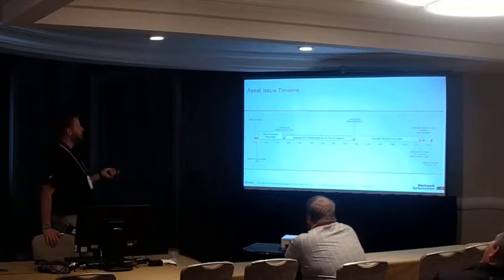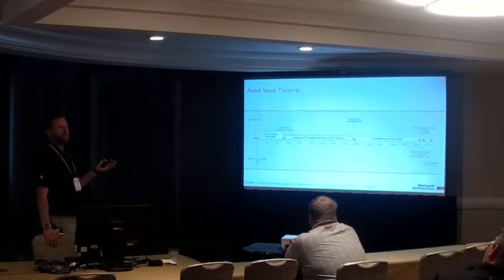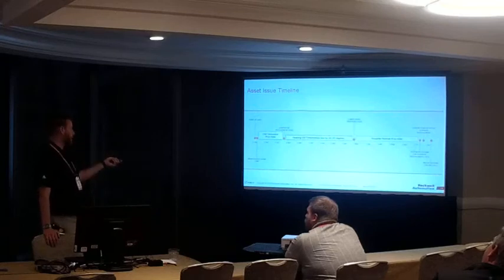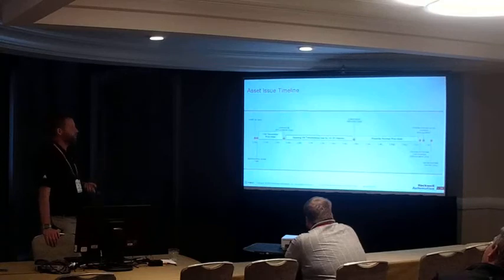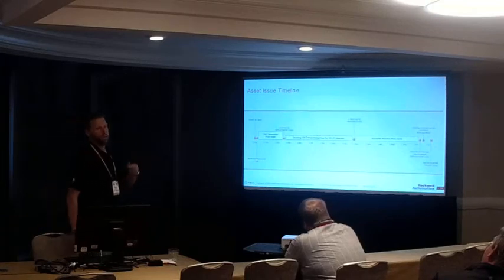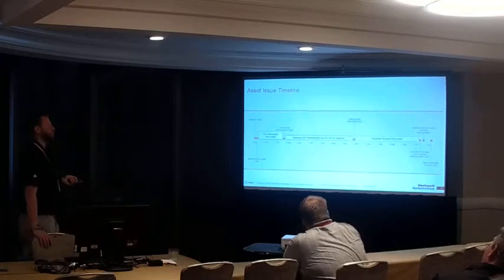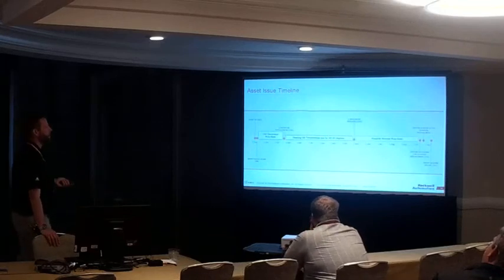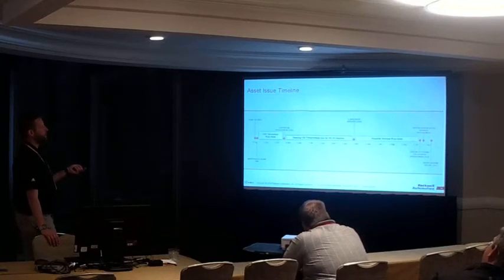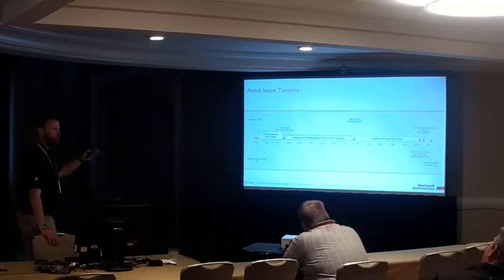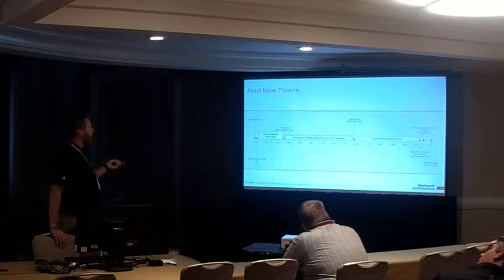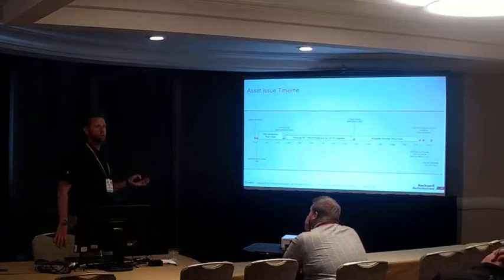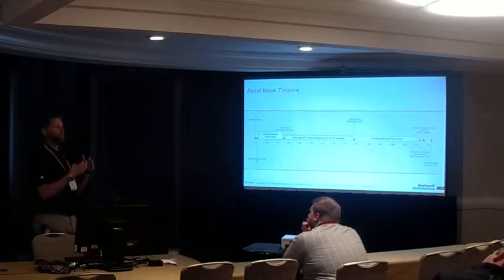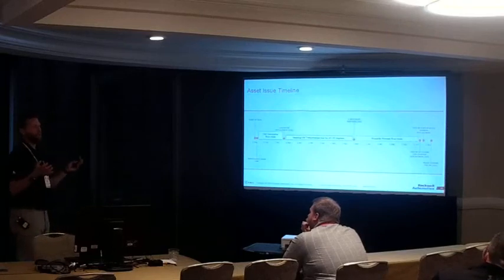So that's actually the root cause of that bearing failure, is the bearing was overheating for a time of over 6 months, right? It was getting substantial mechanical wear because there was more friction going on than there should have been. So the damage is already done, which is why we're not able to detect a failure event. So then we worked with the customer to dig in and said, okay, why would that temperature sensor go down? What's the context? And we provided that context to them and said, hey, this is what we're seeing.